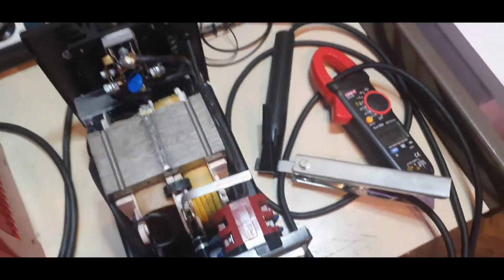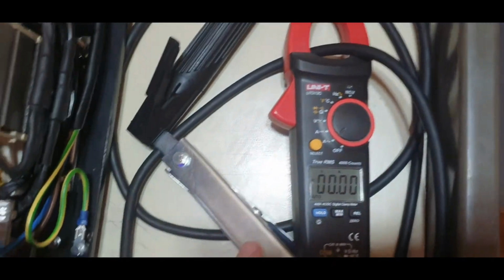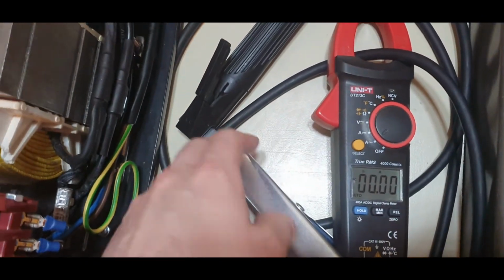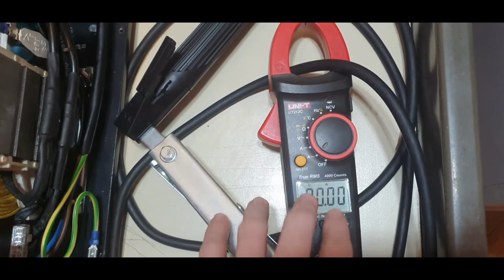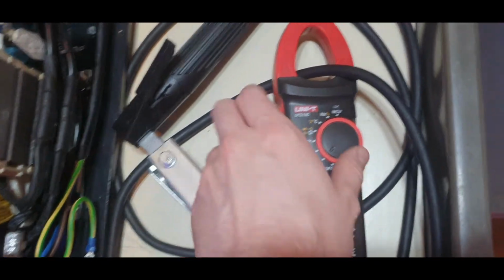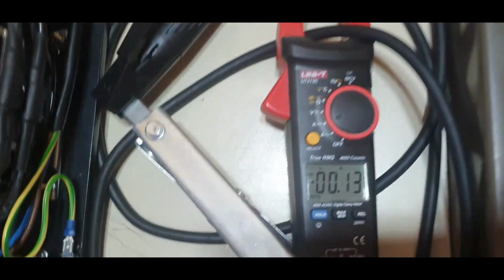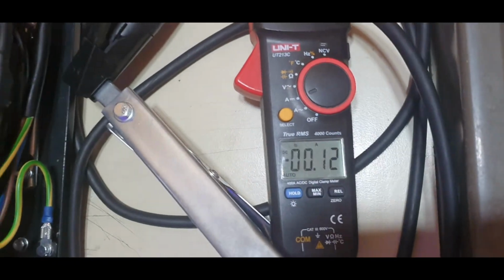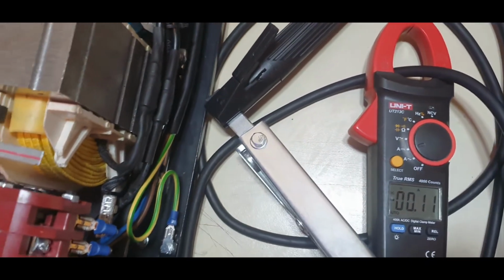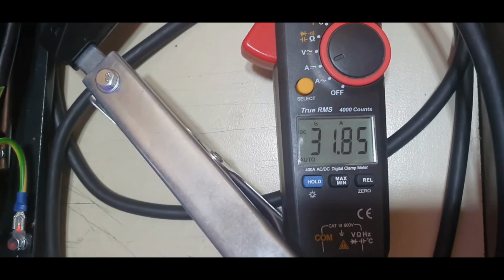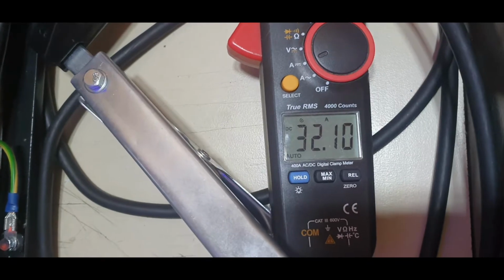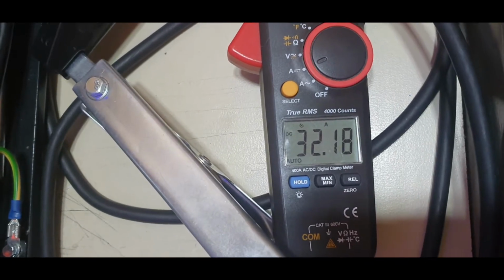Let's turn it off. Okay, I just shorted out the output with this metal piece, and the clamp meter is set to amps, AC... oh sorry, no, it has to be DC of course. My mistake, it's now set to DC, fully closed magnetic shunt, again 230 volts applied to the primary. And the short circuit current is 32 amps.